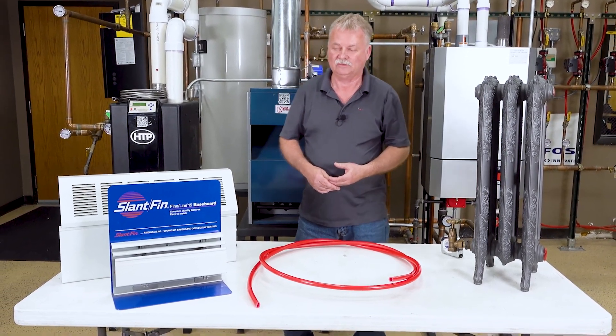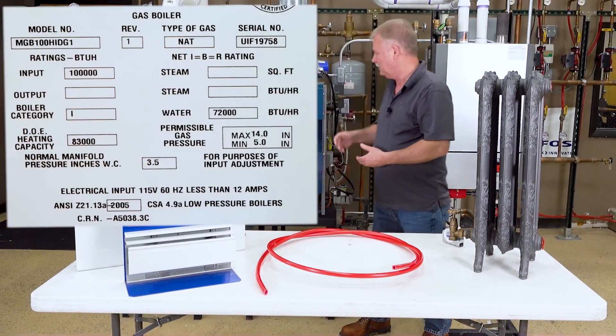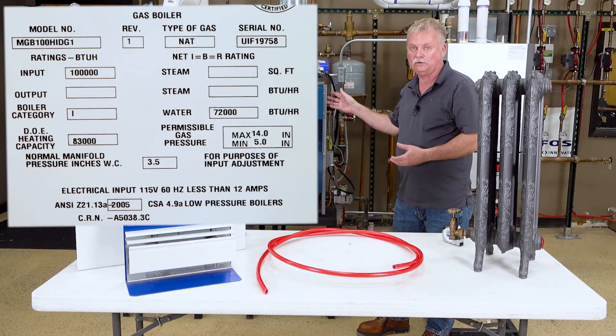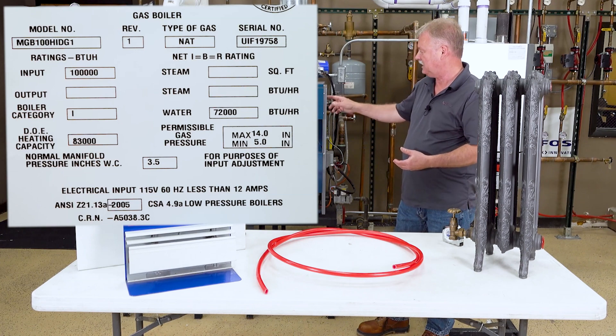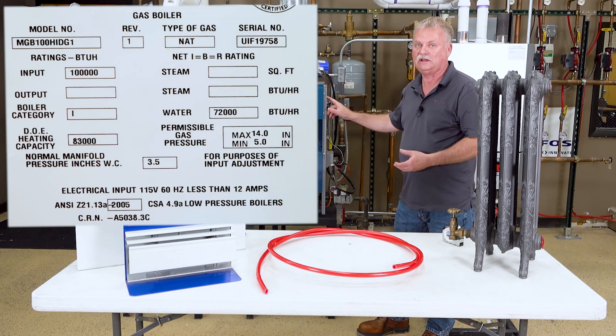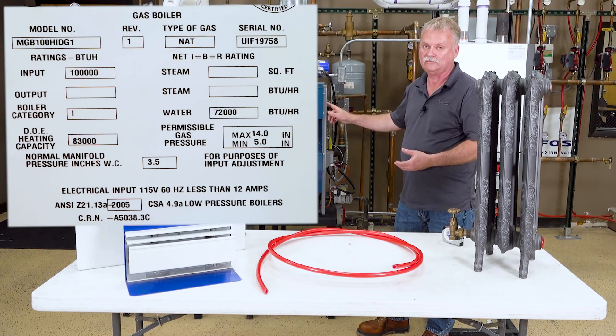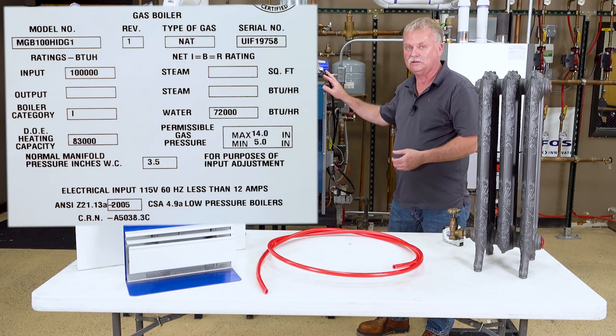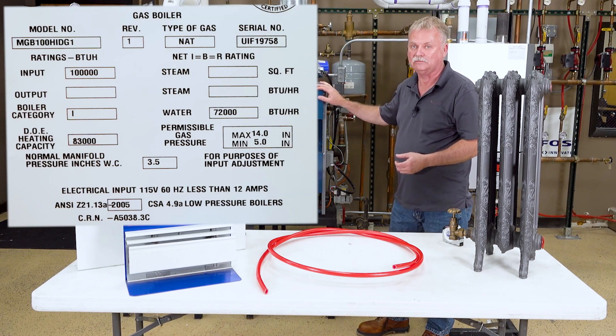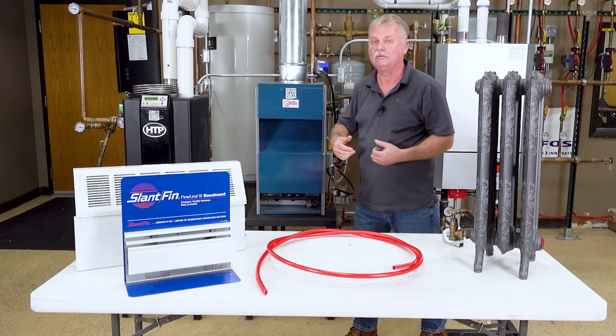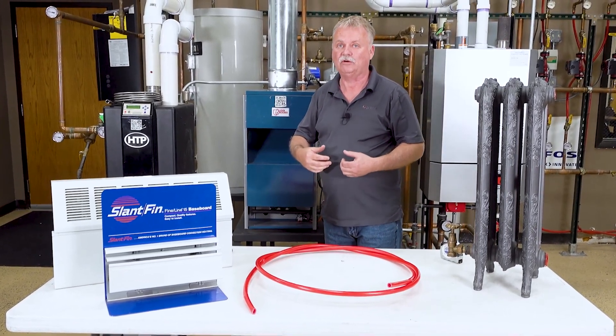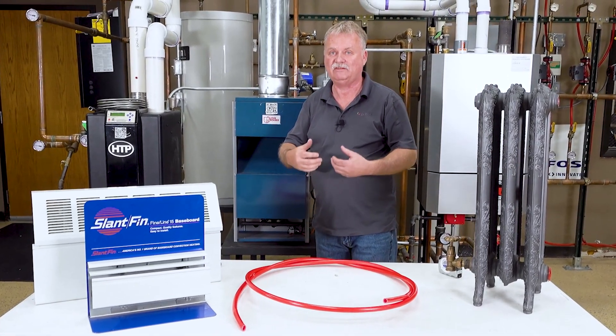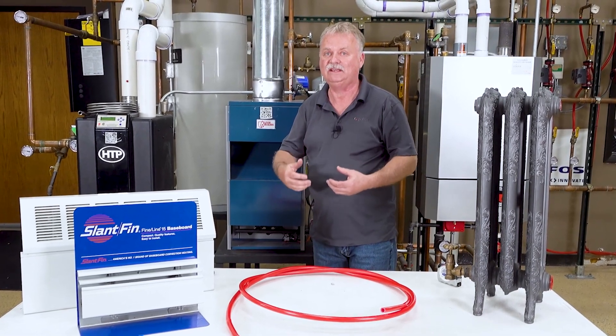The second method is the tag method — go to the boiler room and look at the actual tag on the boiler. In this case, the boiler's input is 100,000 BTUs and its output is 83,000 BTUs. Is that correct for the boiler? Yes. But is that correct for the building? A lot of times boilers are oversized because people want to be safe and make sure they have enough heat.